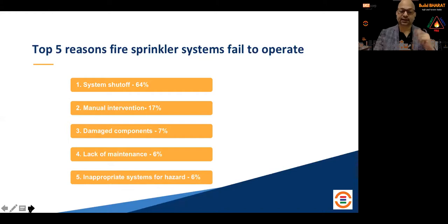And then the last and final reason is an inappropriate system for the hazard. That's when it's important that if you find any gap in shop drawings, you need to revisit and change the design. Because at that time, maybe that area was just an accounts office, but now all of a sudden architects have decided that the accounts office is to be converted into storage. Then how do we deal with that? Is the same detector, the same sprinkler, going to do that? No.